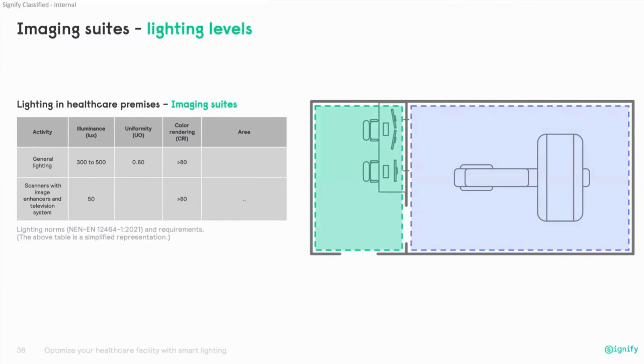Yes, thank you, Ramon. Those are the two norms, or actually it's one norm for imaging suites. Basically, the general lighting should be around 300 lux at minimum and 500 as max, according to the European norm. Uniformity should be 0.8, which is quite high, and the color rendering more than 80.